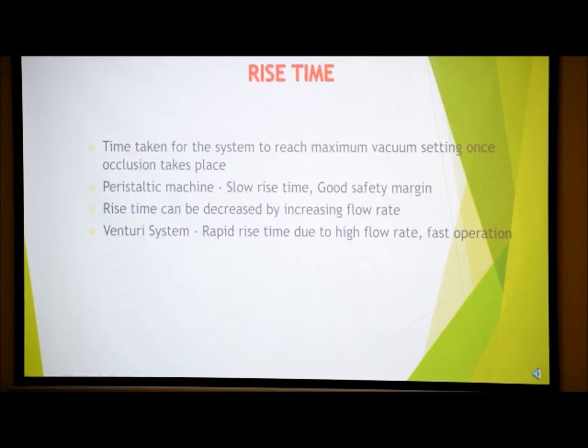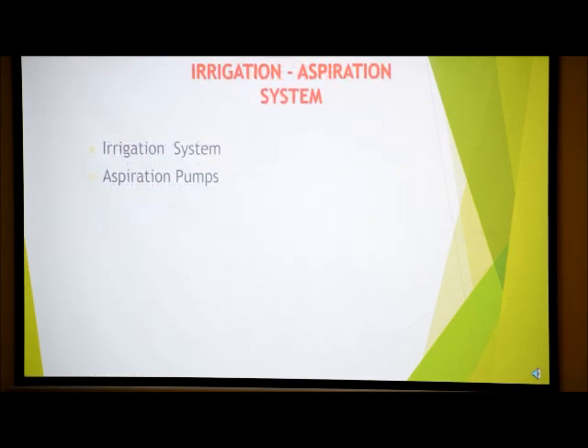Rise time is a concept the surgeon should be very familiar with, because if the rise time is very low, the machine is very fast. If the rise time is more, the machine is slow, and it is always advisable for beginners, because with very fast machines you are more prone to commit blunders. Venturi system has a rapid rise time due to high flow rate, and for a very skilled surgeon the venturi system is safe and very fast. The machine, apart from the phaco handpiece, has an irrigation aspiration system.